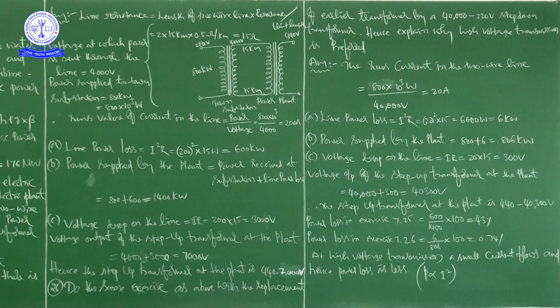Now let's see the answer. The RMS current in the two-wire line is calculated. Since this problem links to the earlier one, we take the same value, 800 kilowatt, that is 800 into 10 to the power of 3 watt, divided by 40,000 volts, giving us 20 amps current.